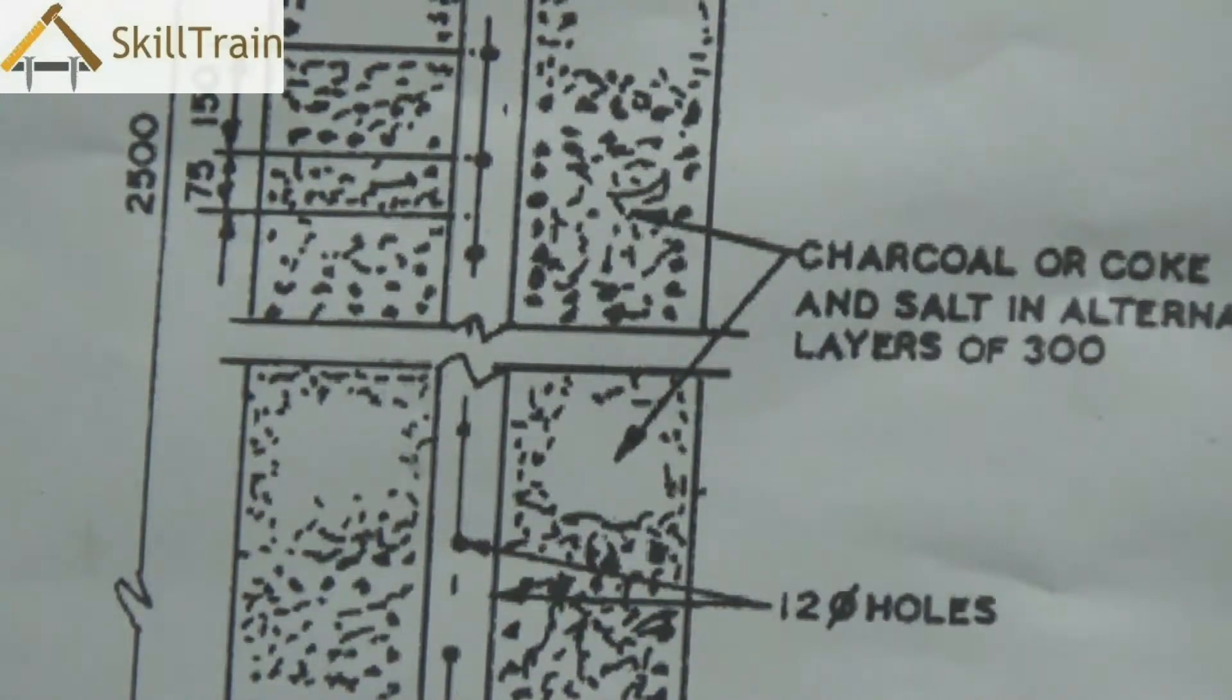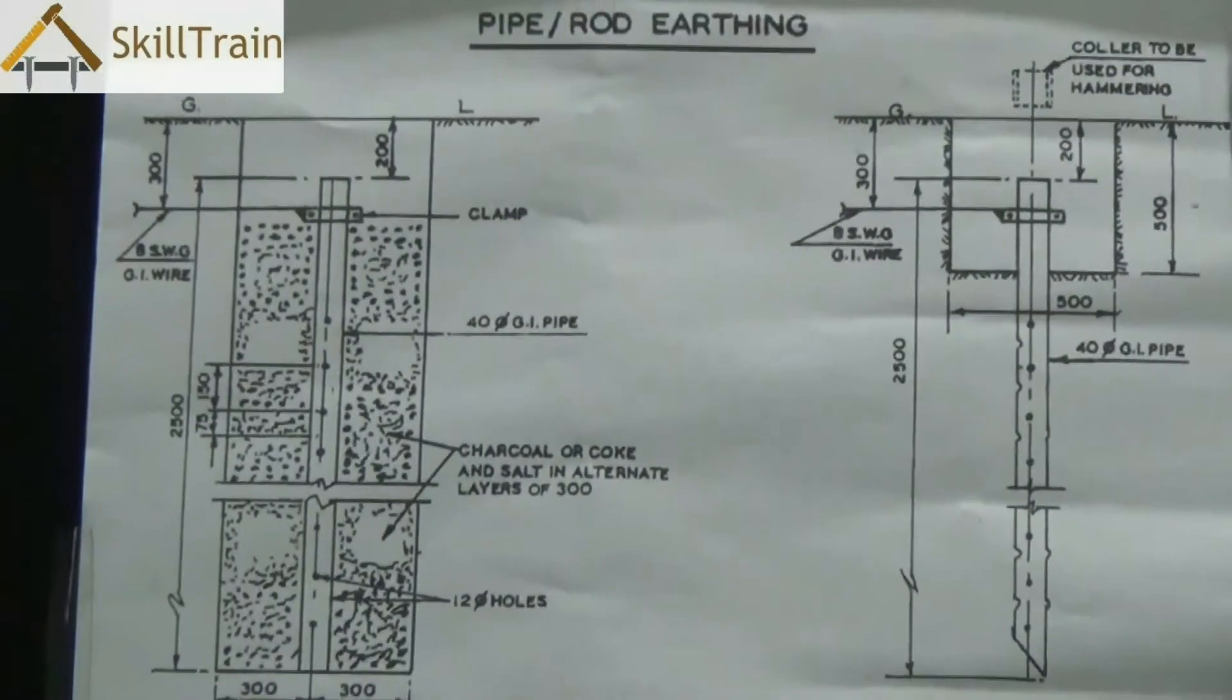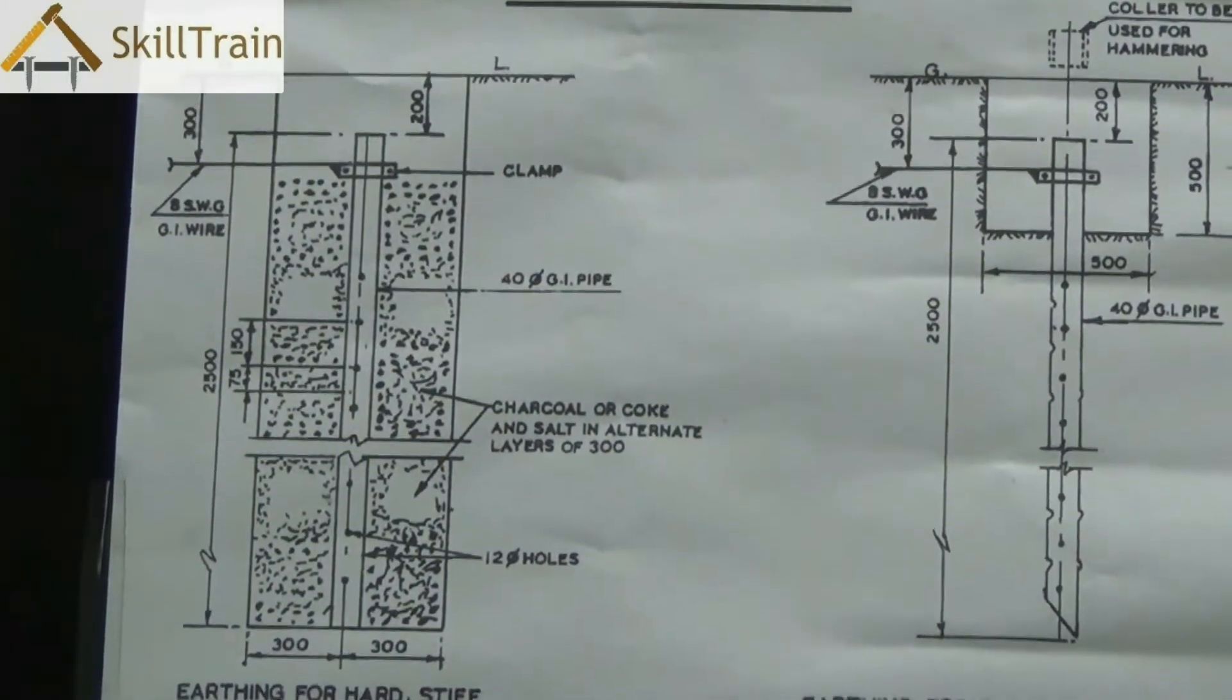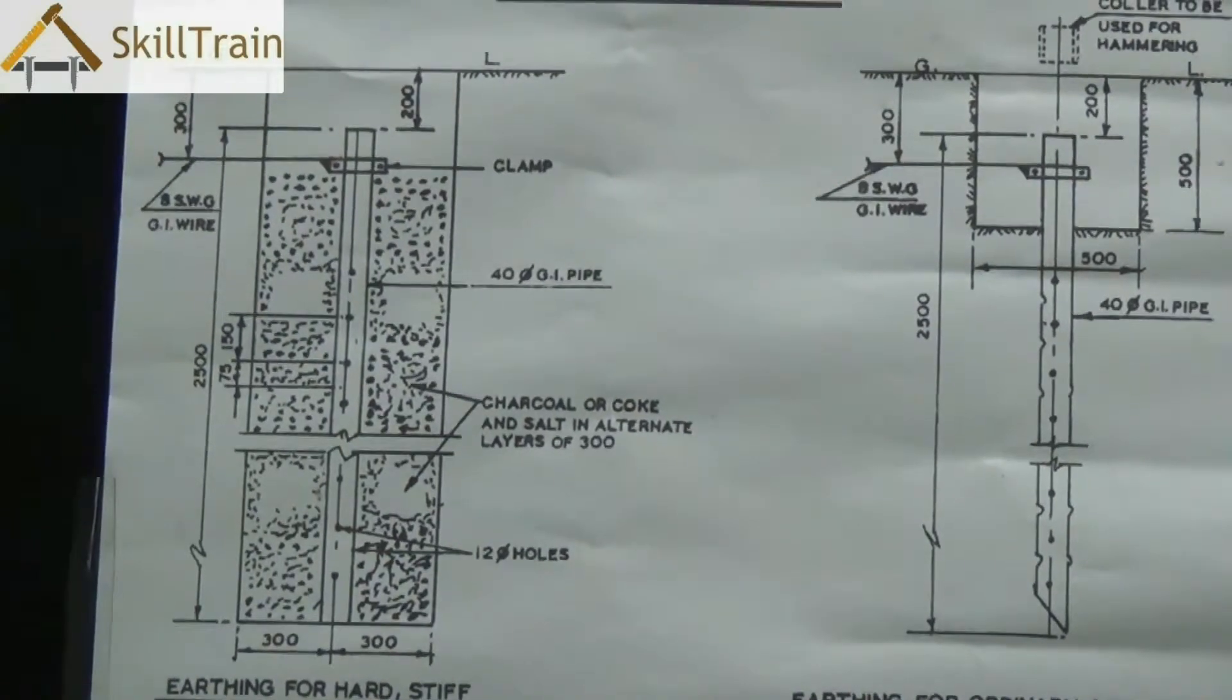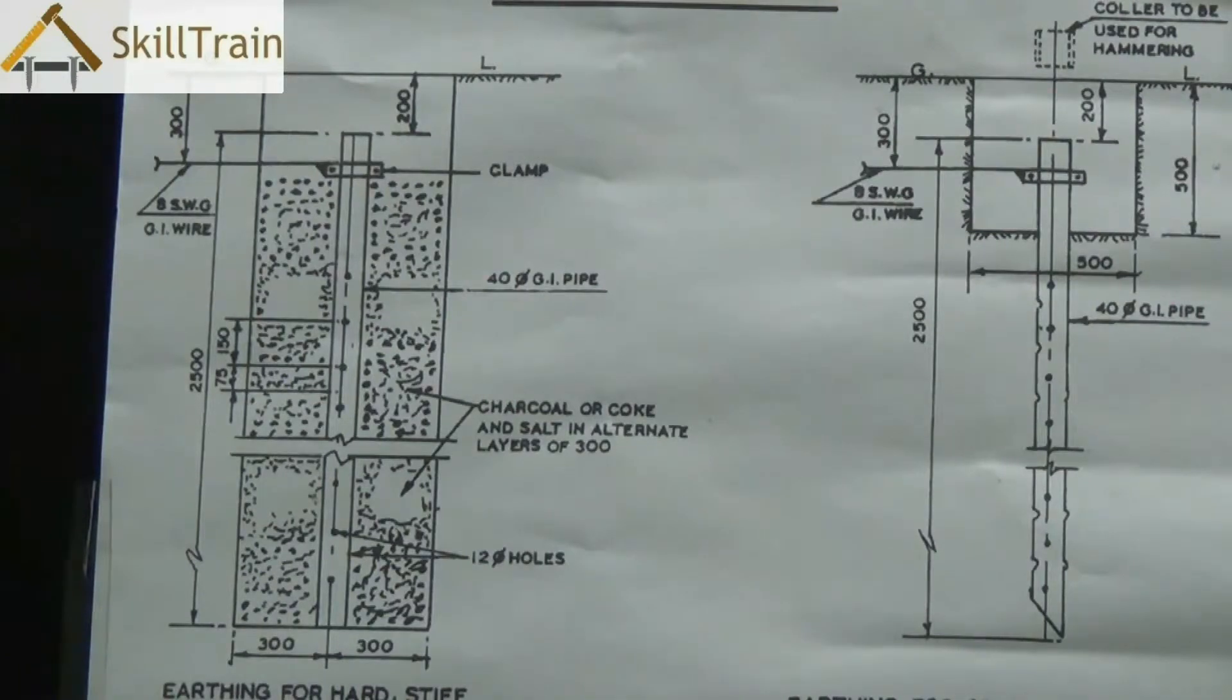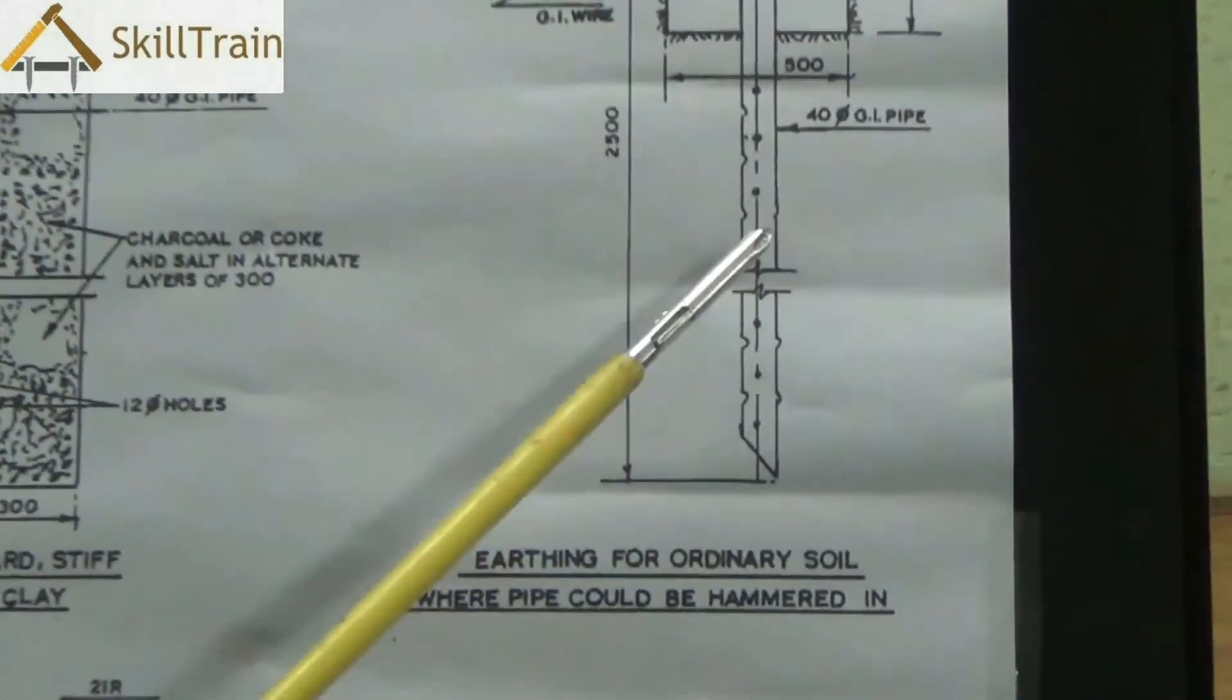This procedure of pipe earthing is far easier to do because you can straightaway insert a full GI pipe of 40 millimeters diameter straight into the earth. If it's a moisture surface, you don't need to keep watering it. Whereas if it's a hard surface, you may need to water it once in a while. But the frequency of watering is much lesser compared to the plate earthing style, and that is why this is maintenance free.